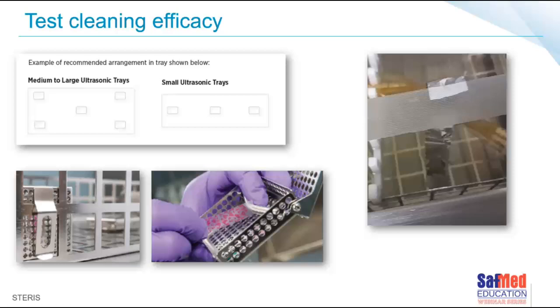Our technical staff tend to use it quite often. But the foil test is a little bit trickier, of course, because now we've got foil residues in the bath of the ultrasonic cleaner, which adds a little bit of a risk. So these days you can also get cleaning efficacy tests that are readily available from a multitude of suppliers. Ultimately, it is some form of indicator that goes inside a holder, and that holder is then attached to an area of the basket in the ultrasonic cleaner.